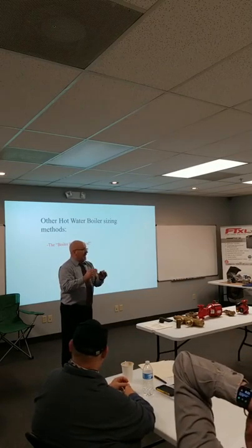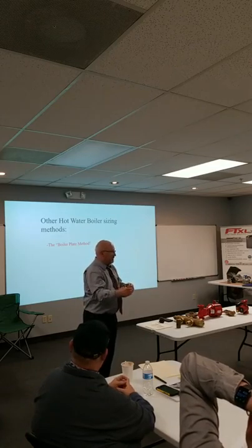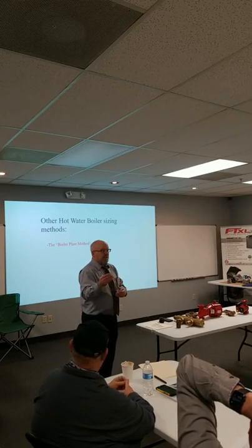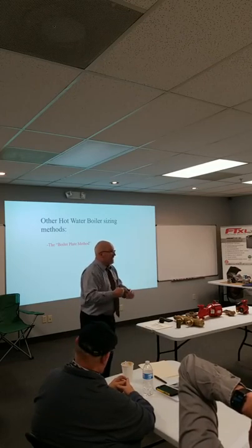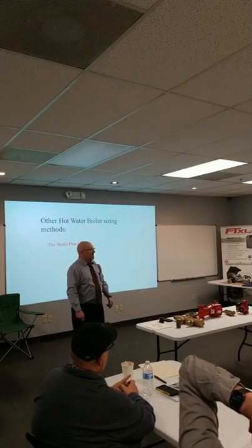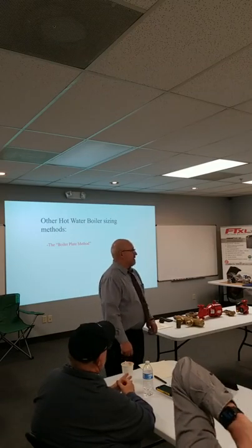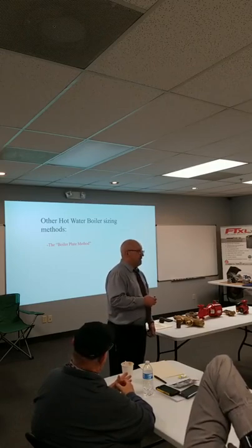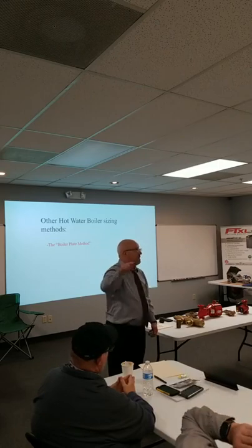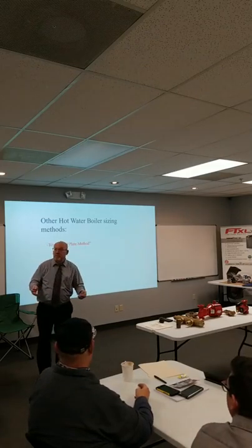If my heat loss at design temperature is 60,000 BTUs, you put a 300,000 BTU boiler in there, it's not going to deliver 300,000 BTUs. It can't. So what does it do? Short cycles. It can only deliver 60,000 BTUs. I know you're being sarcastic. If it's cast iron and it's big enough, and you undersize the pump enough, you can crack boiler sections repeatedly year after year. But if you put a big enough pump on, you can heat the neighbor's house and charge them a lot of money. So yeah, boiler selection, we do a lot of weird things.